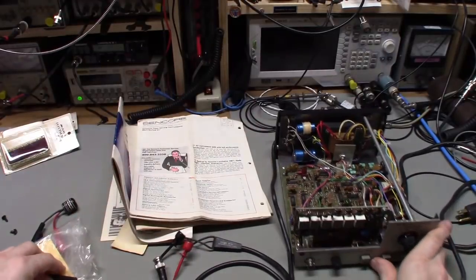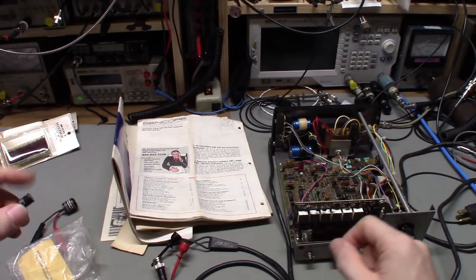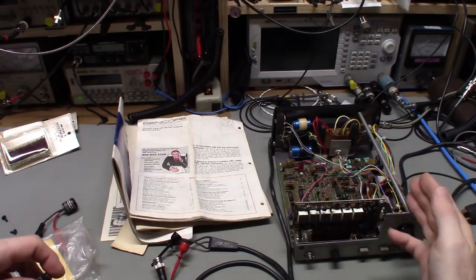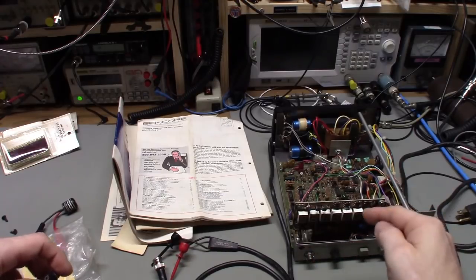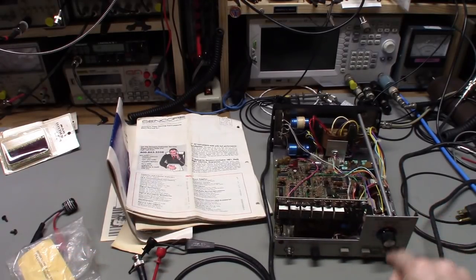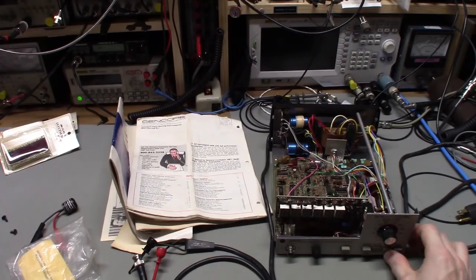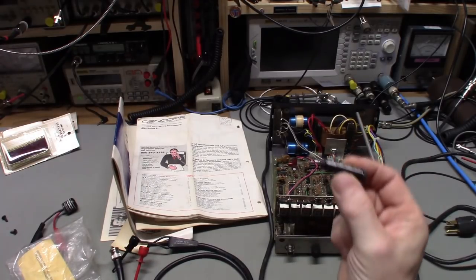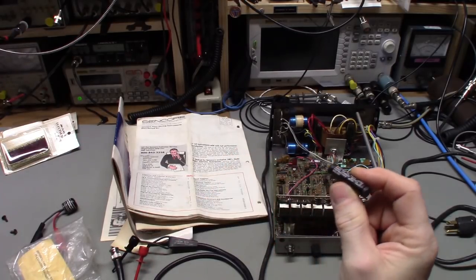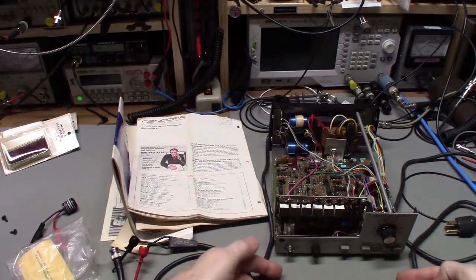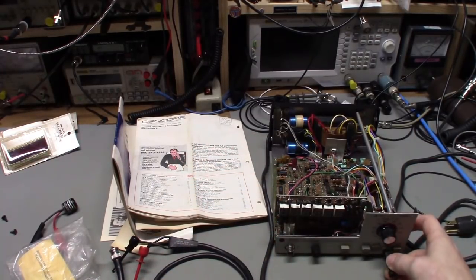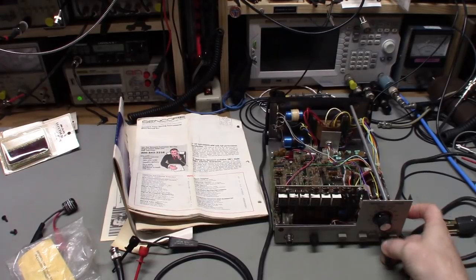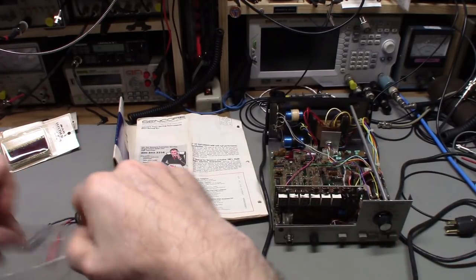If you want to use one of these, which I don't recommend for reforming capacitors, but if you're so inclined, this does produce up to 600 volts on the output, so you can reform capacitors with it. The problem is when you're using the capacitor leakage test, which applies the voltage to the jack here, you have to hold the push button in. It's not a latching switch, it's spring loaded, so you have to hold it in. So they include this little thing, basically a piece of plastic with a rubber bumper on each end, and when you have it in the cabinet and the bail handle pushed down at the front, you can wedge this in. It's what it's designed to do. You push this in, it pushes the button, and then you drop the handle down in between, and it just holds the leakage button pushed in. That's kind of a novel idea. Like I say, I don't recommend reforming capacitors. If a capacitor's that bad, you just need to replace it.